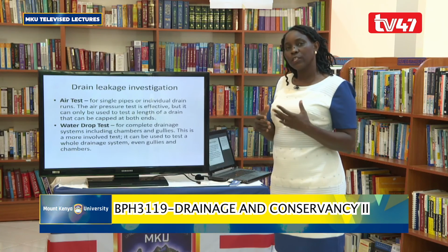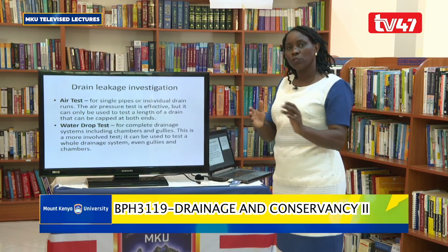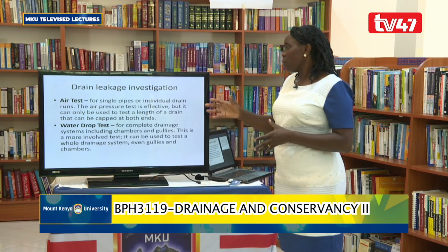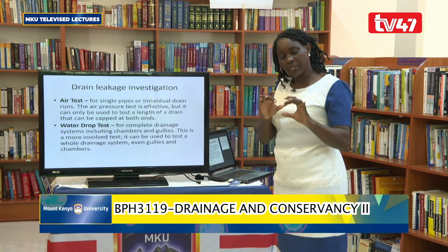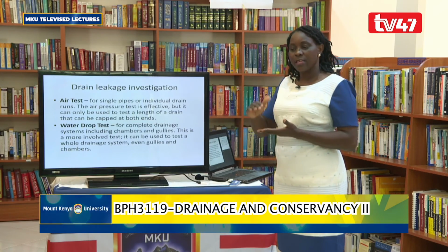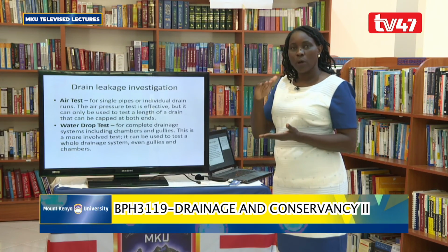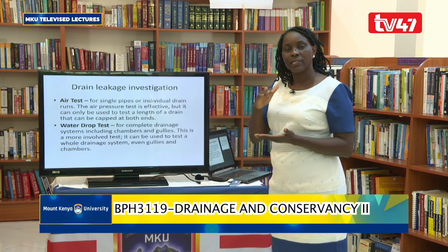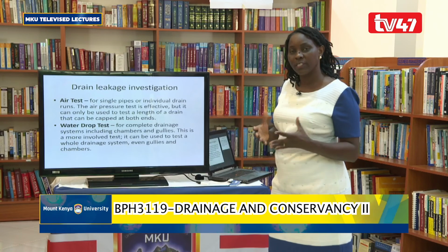It can test a whole drainage system. The water drop test uses water that is pumped into the drainage system, and you observe whether the level is maintained or not. You observe if there is a drop in the level of water that was originally there.